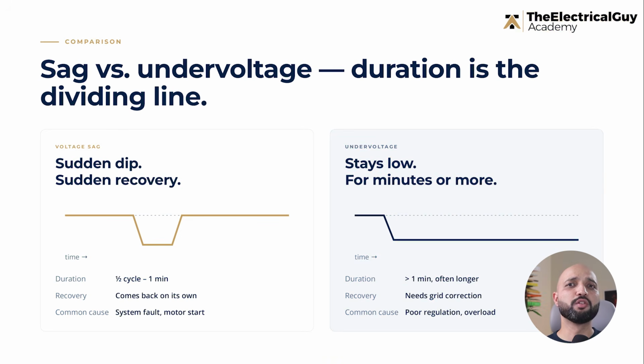Now, do not get confused between voltage sag and under voltage. Under voltage is usually a longer duration condition, typically more than a minute. For example, if a supply voltage remains low for several minutes due to poor voltage regulation or overloaded feeders, that is under voltage. That is not voltage sag. But voltage sag is a sudden dip and a recovery. It comes quickly and it goes quickly. But in that short time, it can create big problems.